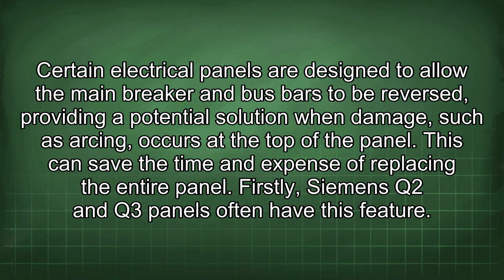Certain electrical panels are designed to allow the main breaker and bus bars to be reversed, providing a potential solution when damage, such as arcing, occurs at the top of the panel. This can save the time and expense of replacing the entire panel.